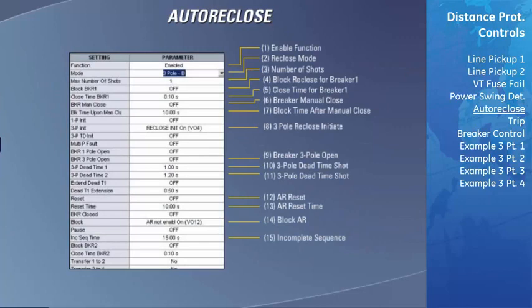Only the settings for three-pole reclosing application for one breaker will be discussed. Set the scheme to enabled if the function should be used. Set the auto reclose mode. Here it is set to 3-pole B, which will reclose 3-pole for all shots of all kinds of faults. Set the maximum number of reclose shots to 1.